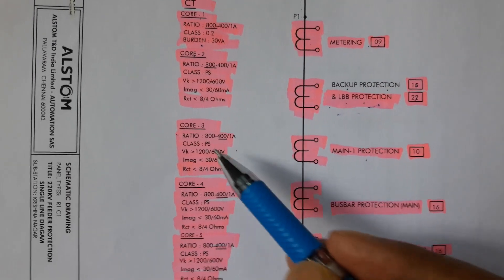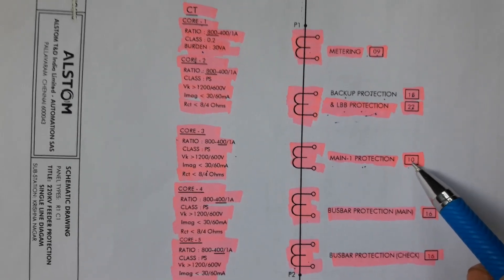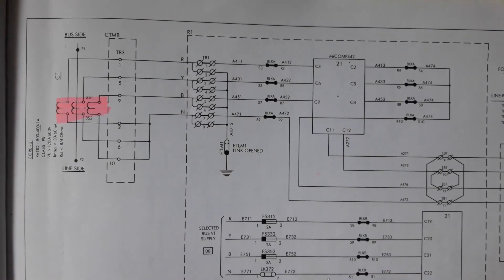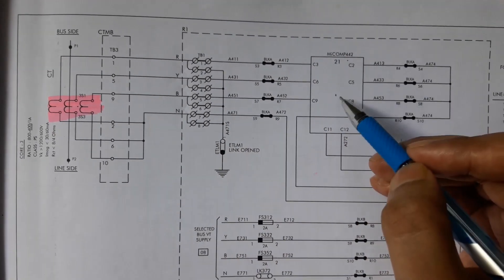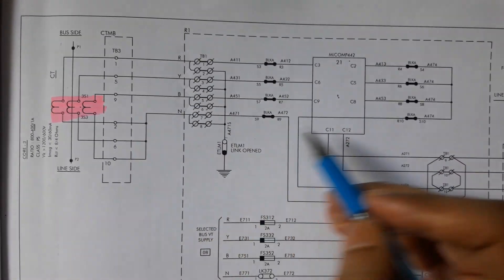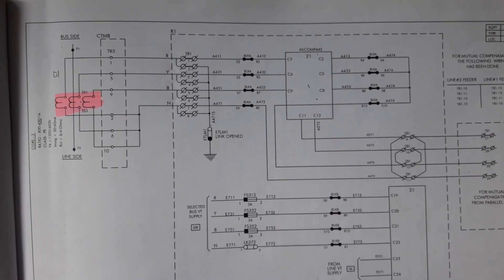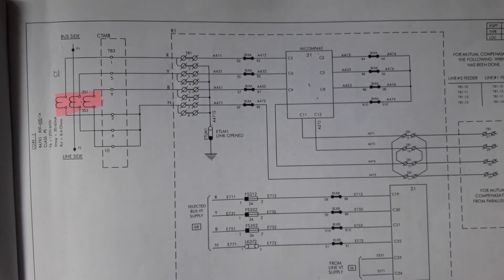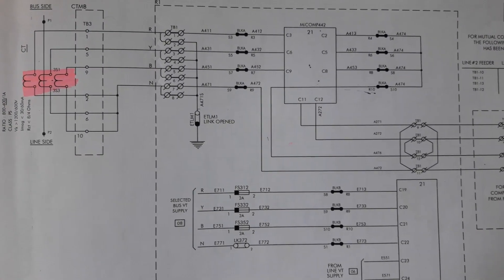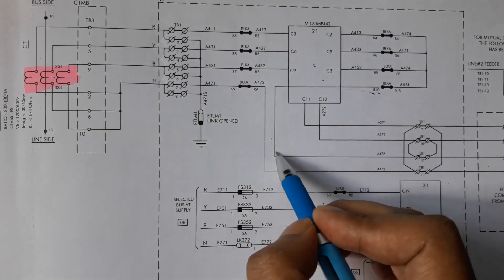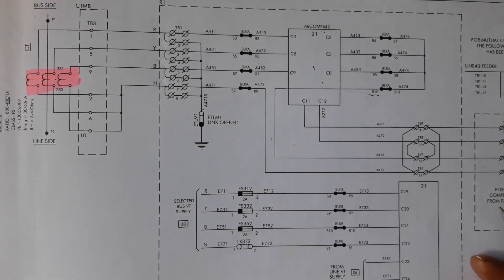The third core of the CT is connected with main zone 1 protection or distance protection, described in sheet number 10. Core 3 is connected to the distance protection relay. The connection is similar to cores 1 and 2, but when a parallel feeder exists, the neutral connection is different — it goes to the adjacent panel for mutual compensation features.